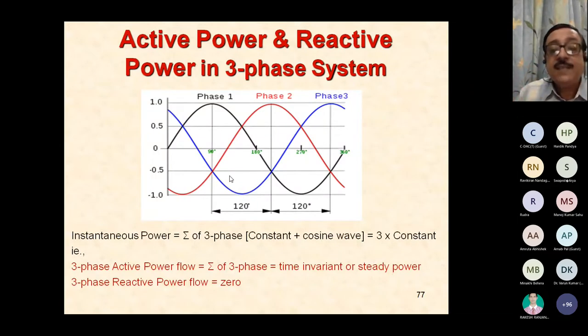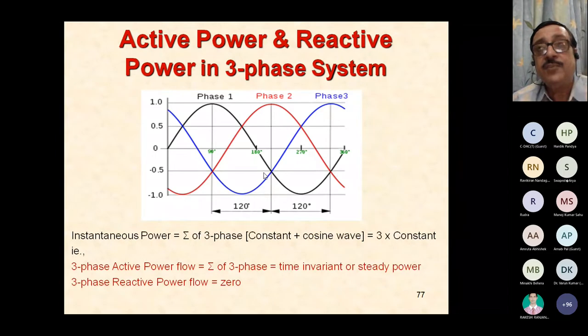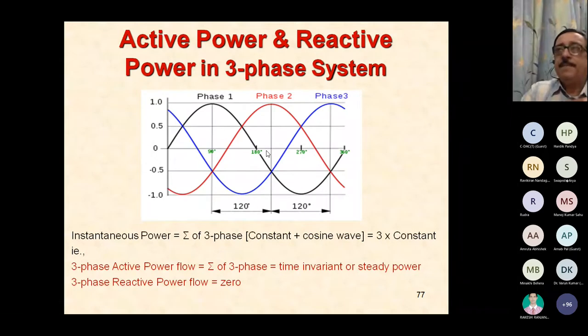But in three phase, there is nothing that will flow into the capacitor because the summation is shown to be zero. See, three single phase AC waveforms displaced by 120 degrees and of the same magnitude sum to zero, so that in three phase, it does not even enter that capacitor, even if the capacitor is there. So therefore, in three-phase systems, the sizing of the capacitor is much smaller than in single-phase systems.